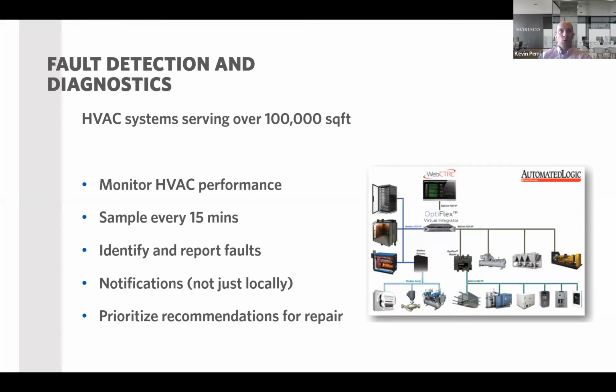And so you might ask what that means. Well, it needs to be able to monitor the HVAC performance, sampling the system's performance at least every 15 minutes. So if you wanted to pick 5-minute intervals, that's completely fine too, but you need to do it at least every 15 minutes. Then it needs to automatically identify and report any system faults, and then notify any authorized personnel of those faults. And it's not just at the building automation system level anymore.